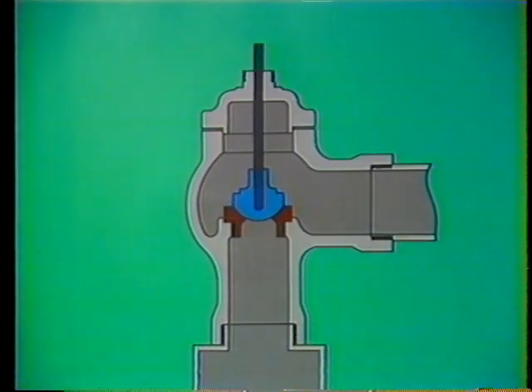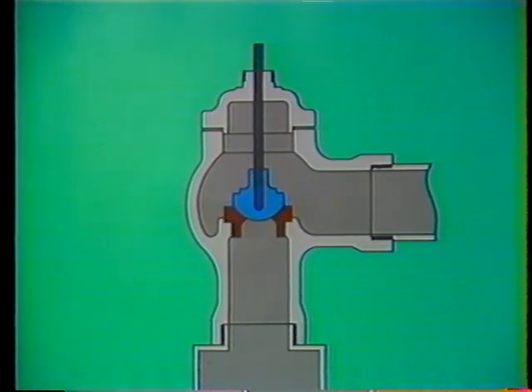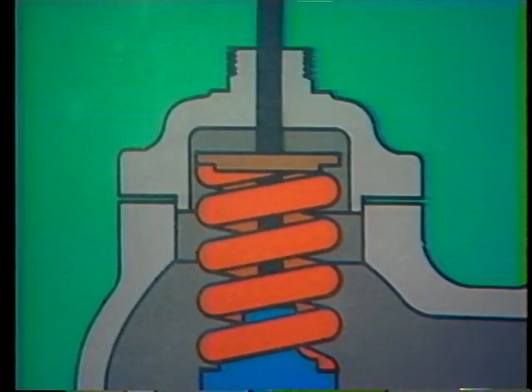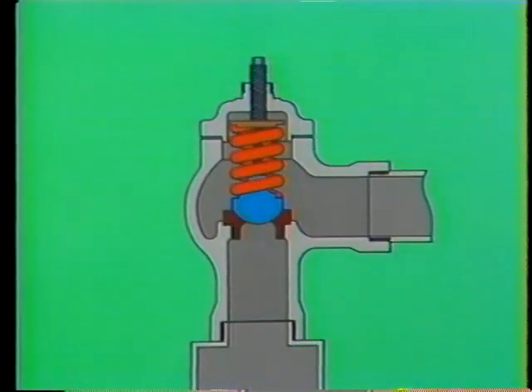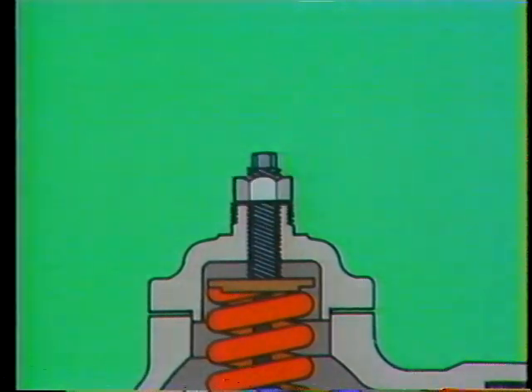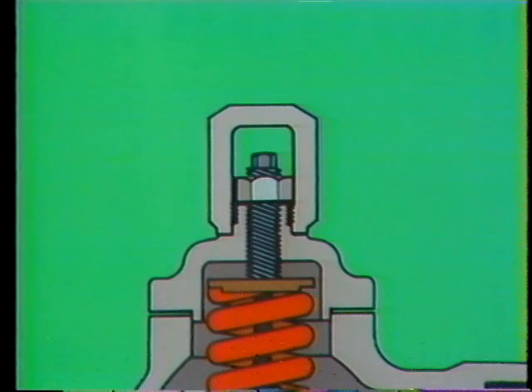Guiding the up-and-down motion of the disc is the spindle or stem. Often it is threaded so it can be screwed directly into the disc. To hold the disc in place against normal system pressure, a spring is used. A spring washer forms a flat surface on top of the spring to ensure even contact between the spring and the adjusting screw. The adjusting screw fits down over the end of the spindle and screws into the valve body. This screw exerts downward force on the washer and spring and can be used to adjust the tension of the spring. A lock nut holds the adjusting screw in position once it's been set, and a cap covers the top of the assembly, protecting the internal parts from dirt and damage.